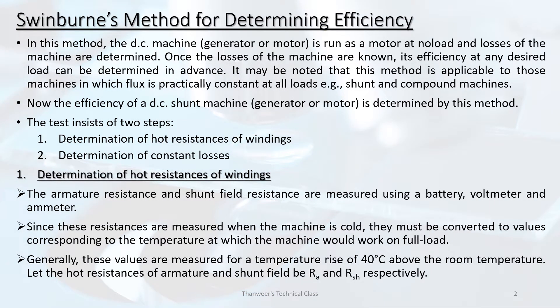Now, Swinburne's method for determining efficiency. In this method, the DC machine — whether a generator or motor — is run as a motor at no load, and the losses of the machine are determined. Once the losses are known, its efficiency at any desired load can be determined in advance. It may be noted that this method is applicable to those machines in which flux is practically constant at all loads.